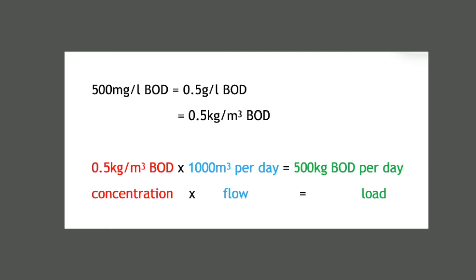And that site, receiving 1000m³ per day at 500mg per litre, handles 500kg of BOD per day — that is the load. Sometimes load data is available and sometimes it's not.